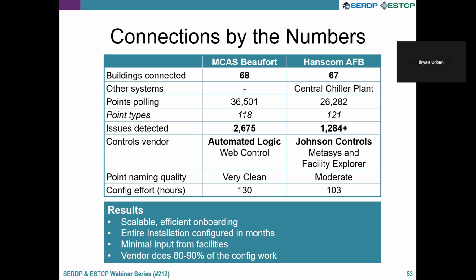Initially we were aiming to get about 12 buildings for the pilot, so we started with about 12. Then both installations asked if Symmetrics could do the whole campus, and they went for it. We got over 60 buildings polling right now, including a central chiller plant at Hanscom, and polling over 25,000 points at each site. Lots of data coming in, very efficient and effective to deploy at scale, without needing to involve the controls vendors at the different sites.